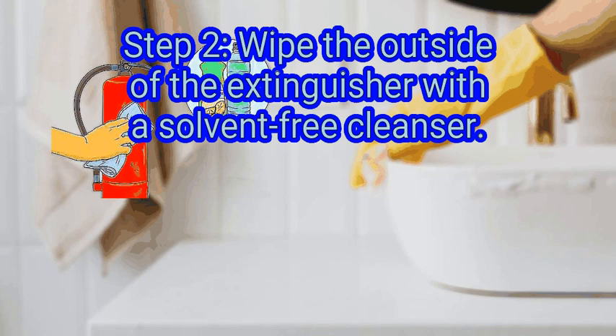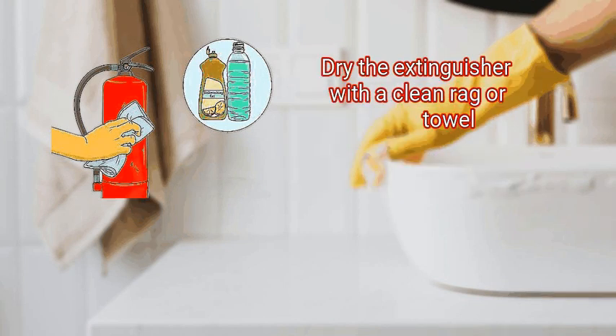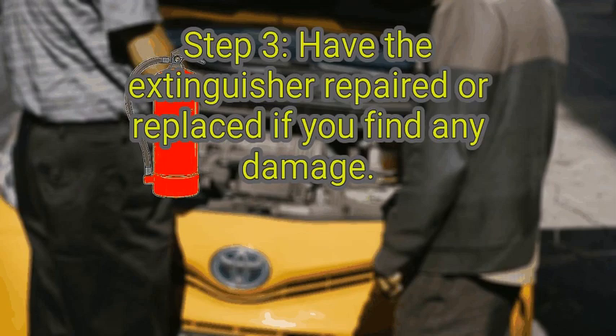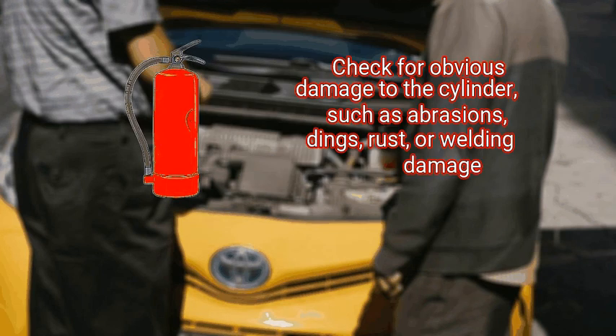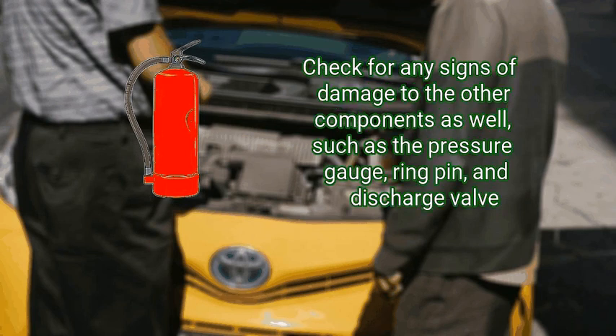Step 2: wipe the outside of the extinguisher with a solvent-free cleanser. Use a clean cloth and a mild cleanser such as warm water and dish soap to wipe down the extinguisher and remove dirt, dust, and grease. Dry the extinguisher with a clean rag or towel. Don't use any solvent-based cleaning products since they could damage the plastic face on the pressure gauge. Step 3: have the extinguisher repaired or replaced if you find any damage. Check for obvious damage to the cylinder such as abrasions, dings, rust, or welding damage.